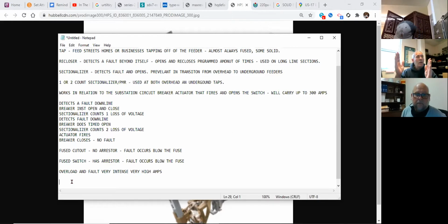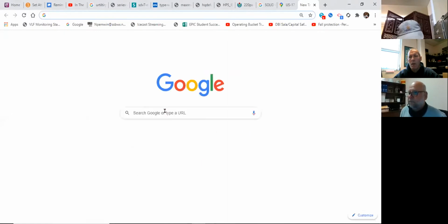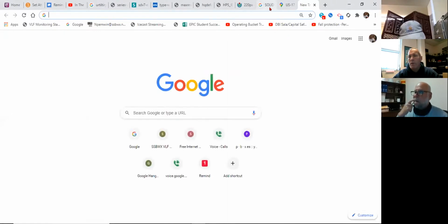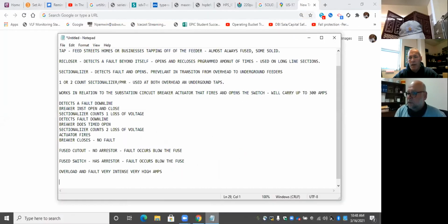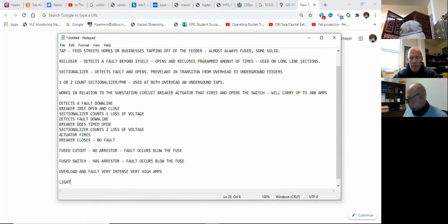Lightning strikes. You guys that have taken the switch apart and down and back up, you'll notice the high side riser comes into the front of the arrestor. What's on the back of the lightning arrestor? Where does that connect to? The fuse? The back of the lightning arrestor. Hold on one second. Next to the pole, right? Goes to the pole ground, correct. So a lightning arrestor truly does not arrest. Was it a lightning ground? It redirects.